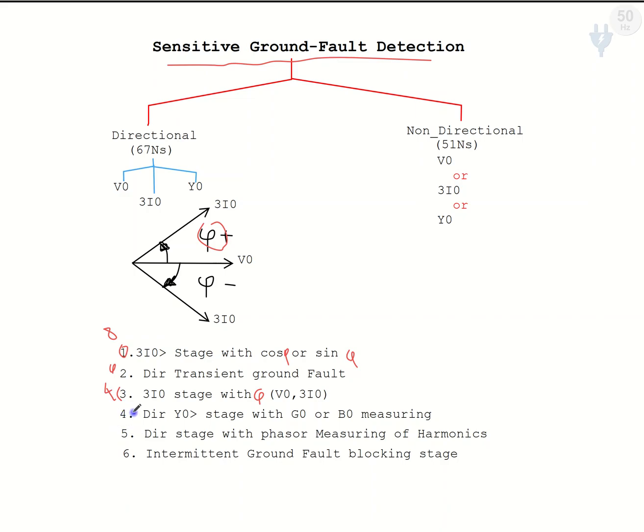In the previous session, we started our discussion about the fourth method — the directional method with the zero-sequence admittance threshold of the system. We discussed that sometimes we use G0, the conductance part of the zero-sequence admittance, or the susceptance part of the zero-sequence admittance for determining the direction. We also discussed what the zero-sequence admittance of the system is and how it is determined.